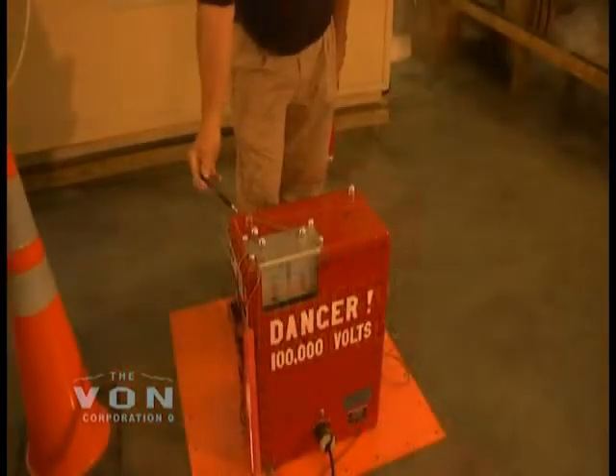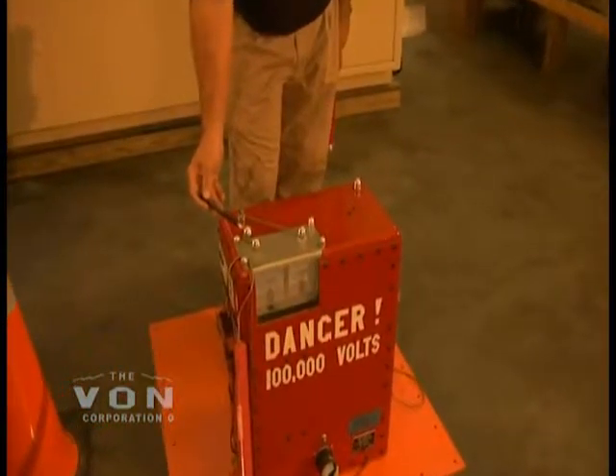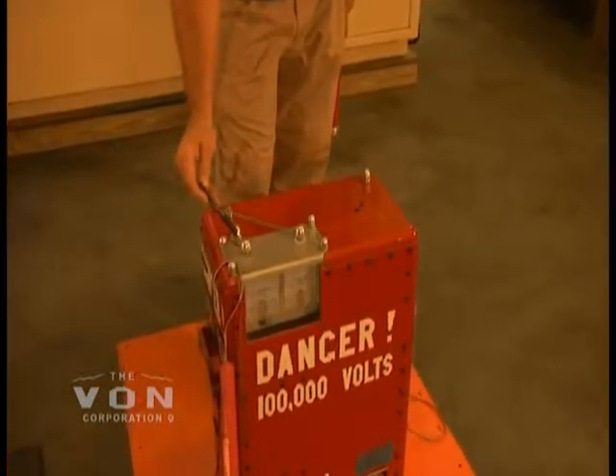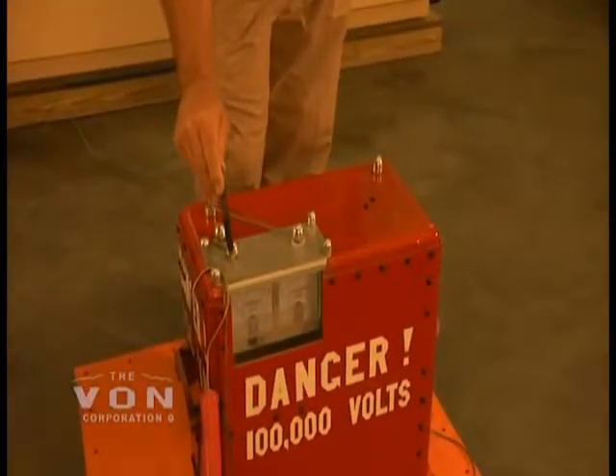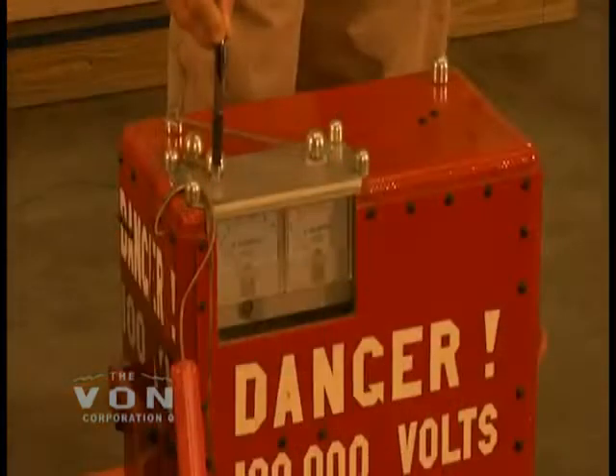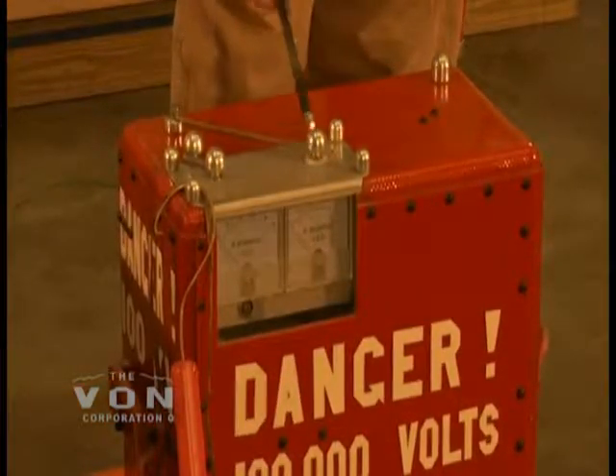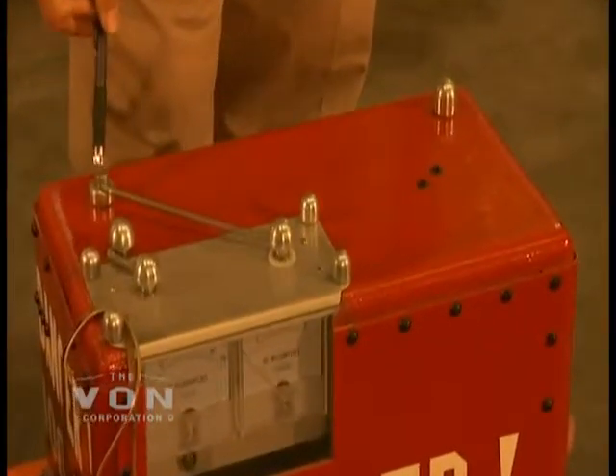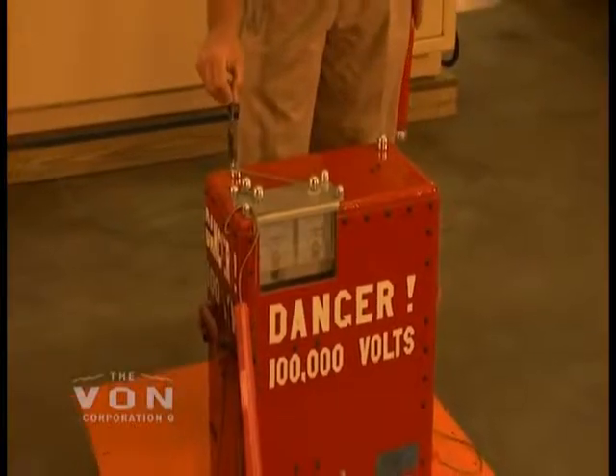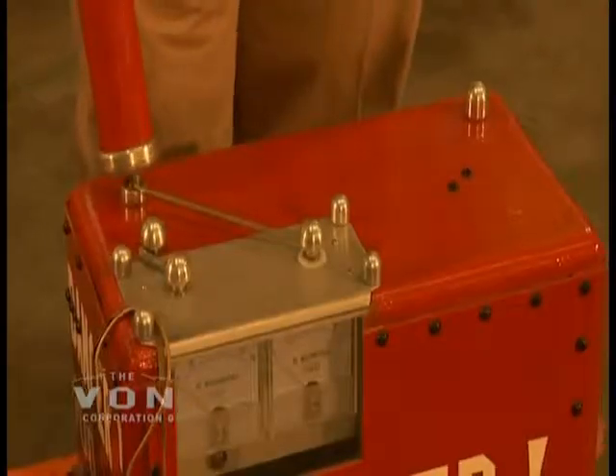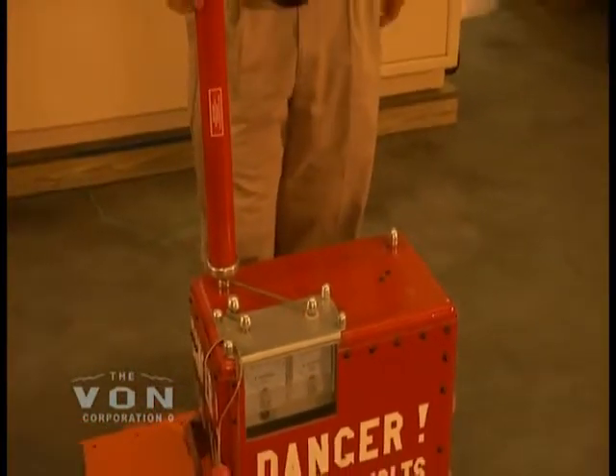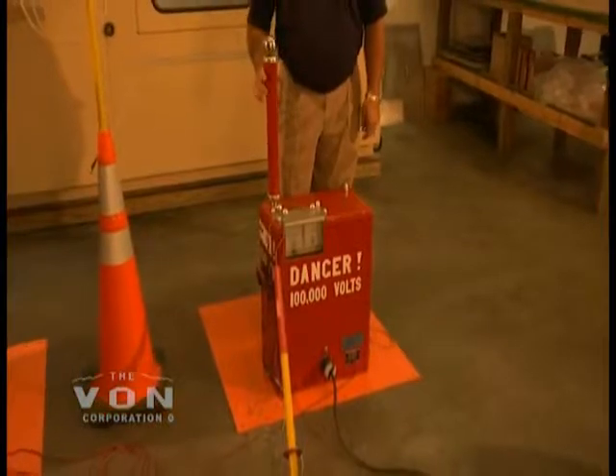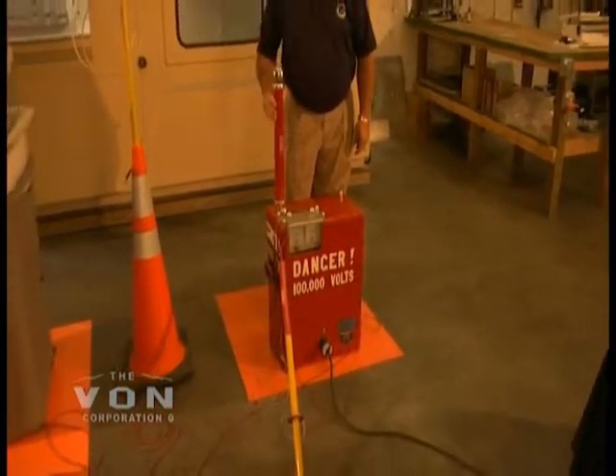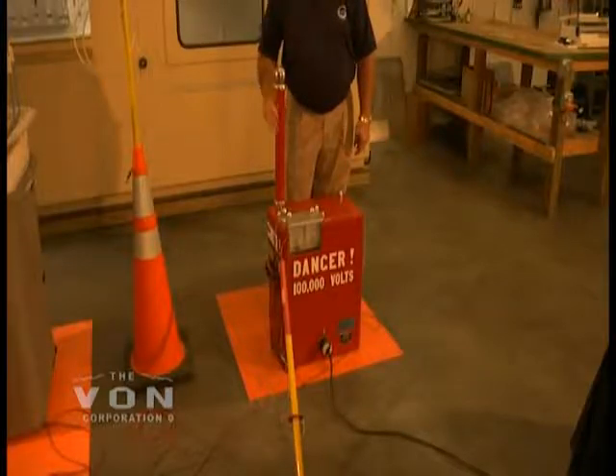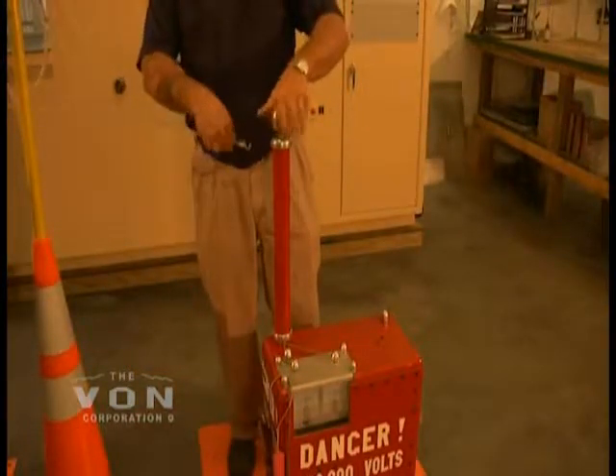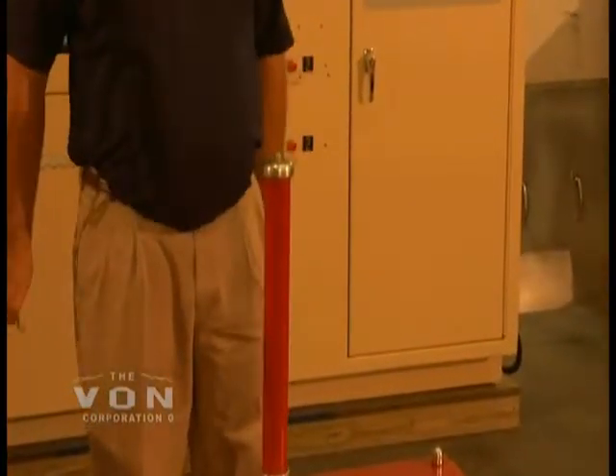This is the high voltage DC output terminal that feeds the hot guard terminal, that feeds the DC microamp meter and DC milliamp meter, that feeds the test terminal. The test terminal feeds the floating terminal. The floating terminal is not connected to anything inside the unit. It is used to connect the protective output resistor that is used to protect the unit while testing, in case something short circuits, so that it'll protect the unit from taking the surge. The corona ball is unscrewed, and this is where all your terminations will be connected.